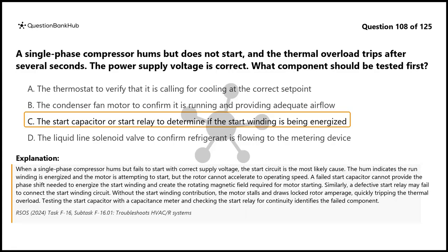Similarly, a defective start relay may fail to connect the start winding circuit. Without the start winding contribution, the motor stalls and draws locked rotor amperage, quickly tripping the thermal overload. Testing the start capacitor with a capacitance meter and checking the start relay for continuity identifies the failed component.